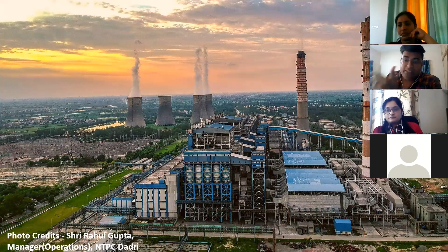Although I'm talking about the control system of GE, because I have worked for GE and I'm still working on GE projects, I can tell the control system is pretty much there to control. Once you hit a start button, it will go till synchronization. You have to just take actions at different points. Once you hit the button, it will go to full speed no load of the gas turbine, and you just click another button. It will go for synchronization, and then one more button, and it will go to base load. Base load is nothing but the maximum load at which the gas turbine can run. So GE's control system is equipped to do that.